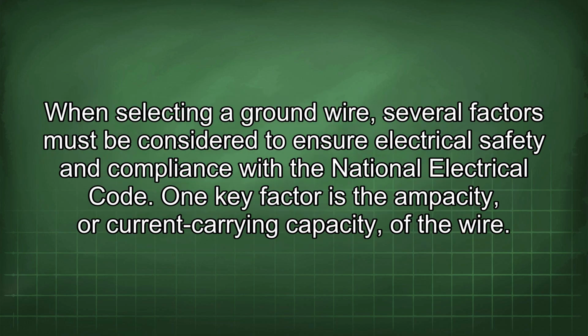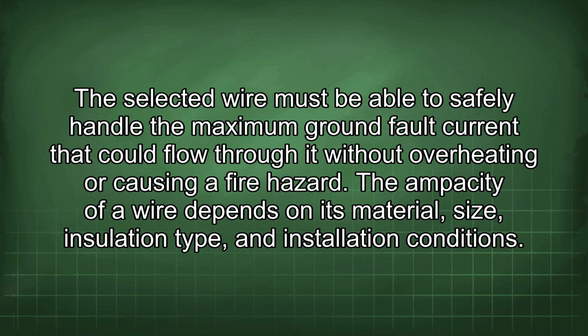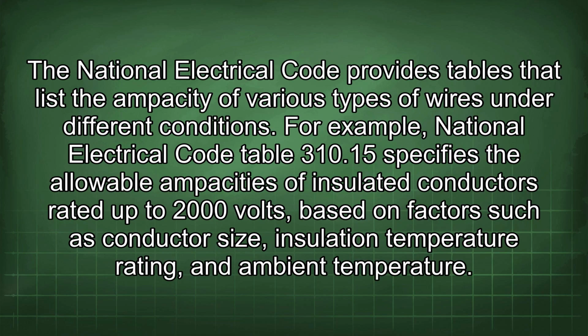When selecting a ground wire, several factors must be considered to ensure electrical safety and compliance with the National Electrical Code. One key factor is the ampacity, or current carrying capacity, of the wire. The selected wire must be able to safely handle the maximum ground fault current that could flow through it without overheating or causing a fire hazard. The ampacity of a wire depends on its material, size, insulation type, and installation conditions. The National Electrical Code provides tables that list the ampacity of various types of wires under different conditions. For example, National Electrical Code Table 310.15 specifies the allowable ampacities of insulated conductors rated up to 2000 volts, based on factors such as conductor size, insulation temperature rating, and ambient temperature.